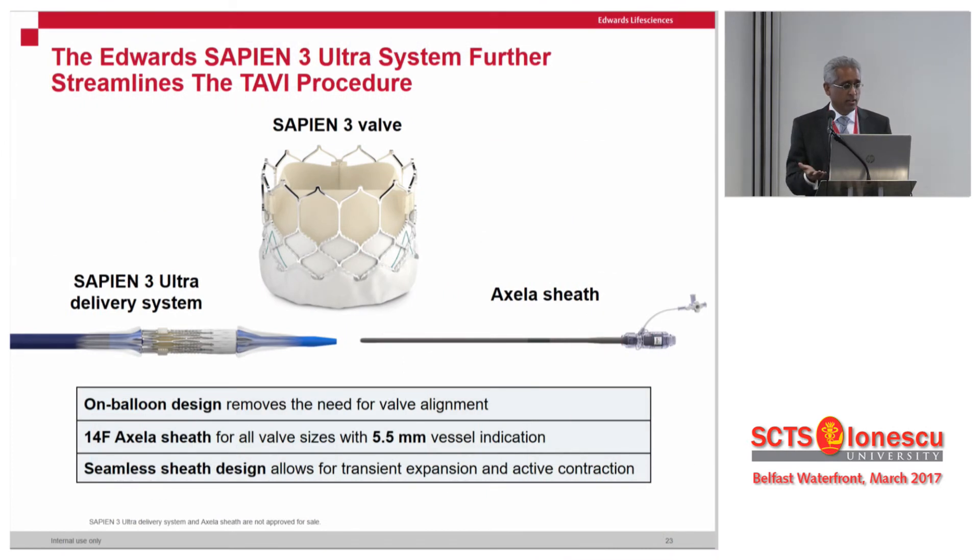The next generation of Sapien will build on Sapien 3 but will be preloaded and have a much lower profile, with the Axela sheath coming down to about 14 French equivalent — a huge step compared to the earlier 18, 19, or 22 French devices.